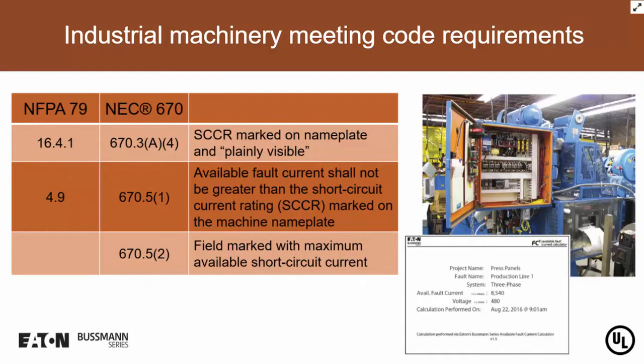We also have a requirement for the available fault current to be marked on the machine nameplate, and that's in NFPA 79, Chapter 4. We also have that in NEC 670.5(1). And then the NEC has a requirement that's not in NFPA 79, because NFPA 79 basically deals with just the construction of the machinery, whereas the NEC deals with the application of the machine in the field. There is a requirement that machinery needs to be field marked with the maximum available short-circuit current. And, of course, that can only be determined in the field.